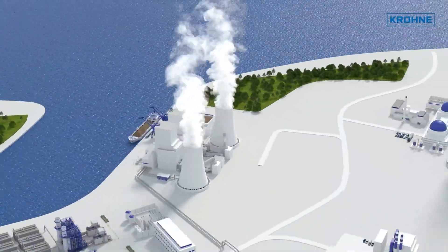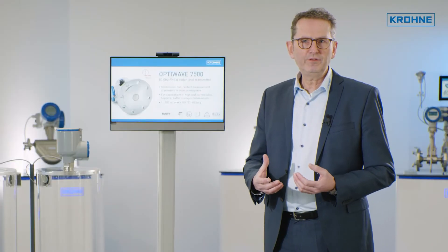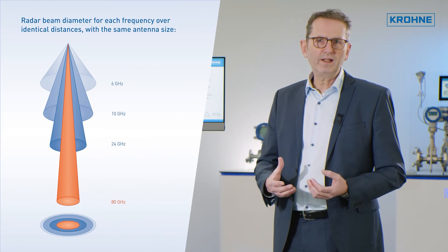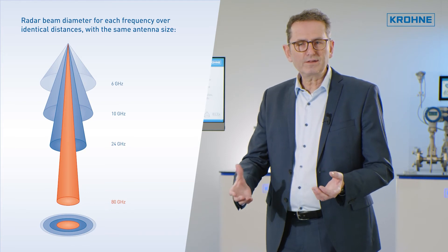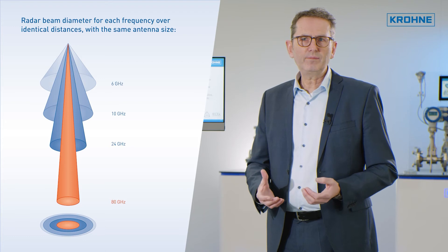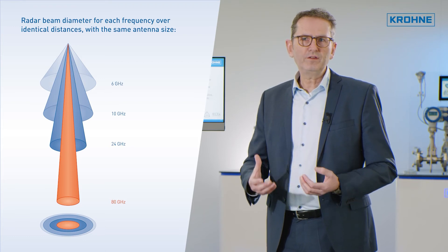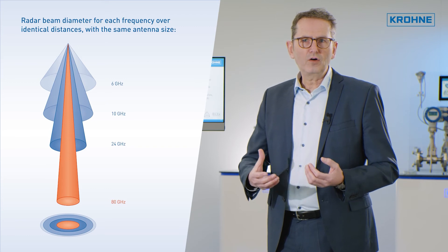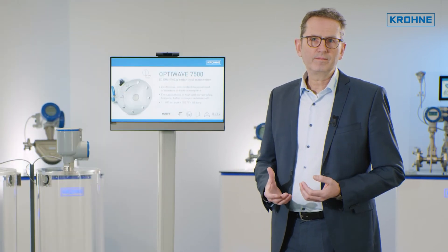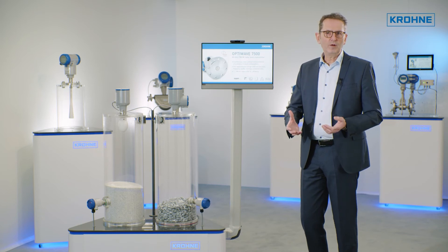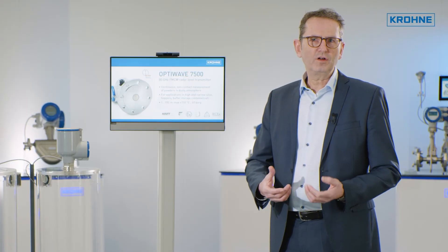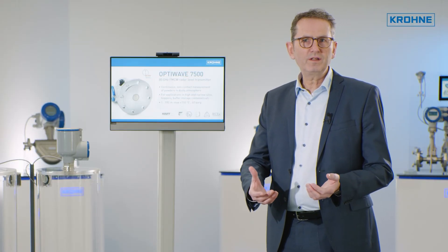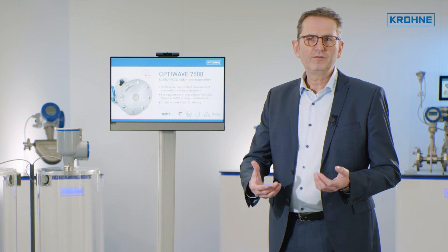The OptiWave 6500 is particularly useful in applications with difficult materials — for example, with low dielectric constants or with high dust content in the gas phase — and delivers stable and reliable results. This means that many level applications can now be achieved that were previously only solved by other mechanical or radiometric measuring devices. Thanks to the clever antenna design of the OptiWave 6500 without metallic horn material, buildup has little chance of interfering with the measurement signal. KROHNE offers a complete product portfolio for level measurement based on FMCW radar technology for almost any application.